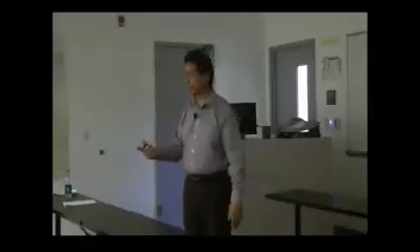And every panel, as we mentioned before, is going to have a panel schedule. That panel schedule identifies your circuits. So part of your construction commissioning activities are turning over all your panel schedules. All the circuitry, what it's feeding, okay, both from your source, being a panel upstream, versus to that particular lighting system, piece of equipment, okay, air handler. Extremely important. Emergencies, there's one segment we cover emergency preparedness in facilities maintenance. Exactly that. If I have an outage, I need to know which circuit was compromised and which pieces of equipment are actually supported by this particular circuit. It's going to give me an indication on load and where I need to start in regards to my evaluation.